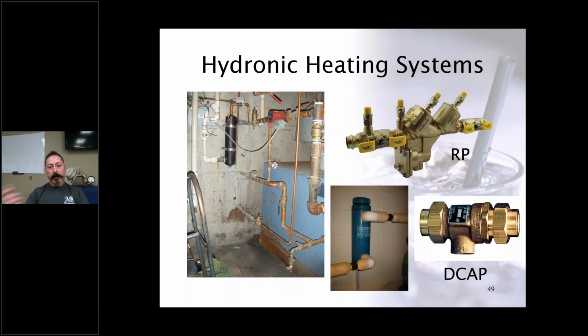Hydronic heating systems will be used for heating buildings or for any industrial application. This one here, that blue thing is where you'd add your chemicals. This is a chemical pot feeder. These are severe hazard boiler type systems, and they would use an RP. Or for makeup lines going to a heating system without a chemical in it, constructed out of potable piping like copper, you'd only need a dual check with atmospheric port. So again, you really have to know the application, the cross connection, and your backflow preventers to make the right choice of the backflow preventer you need.